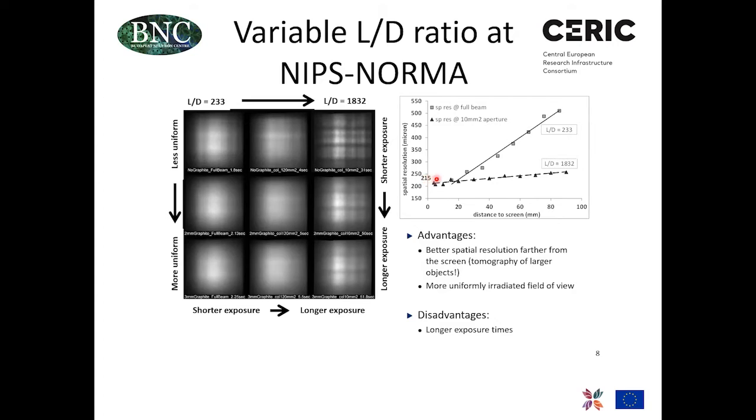As you go farther and farther away from your detector with your sample, the beam properties will become dominant in the image blurring. If you have a very nice and parallel beam of neutrons, like in this case, then the contribution of neutrons to this blurring will be moderate, and there will be no significant difference between, let's say, the front side and the rear side of the object.